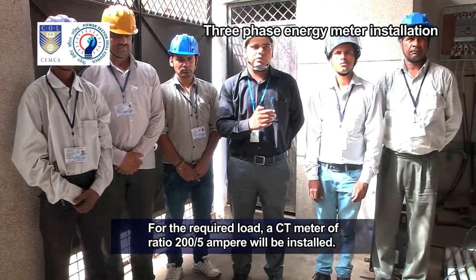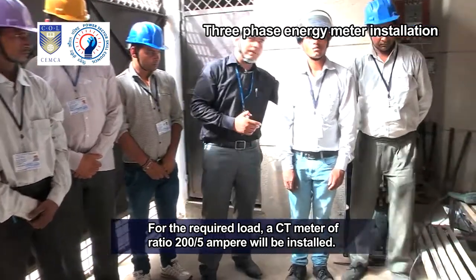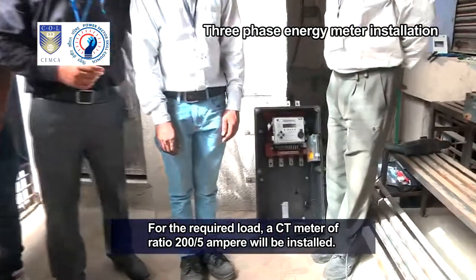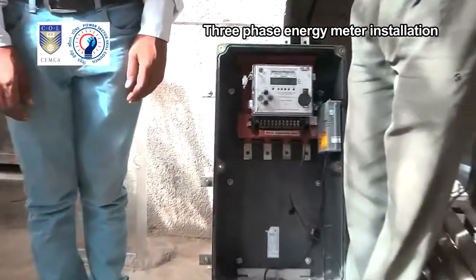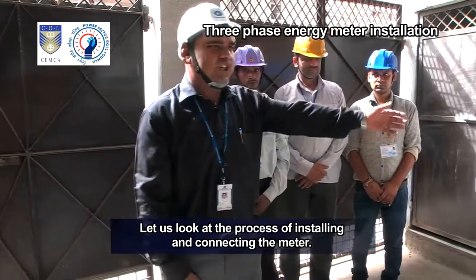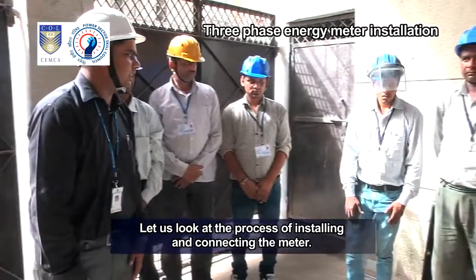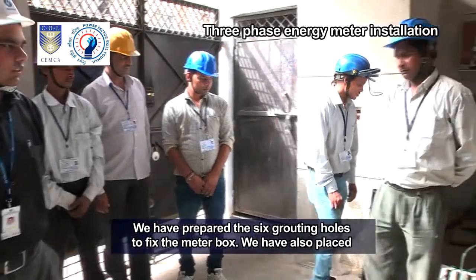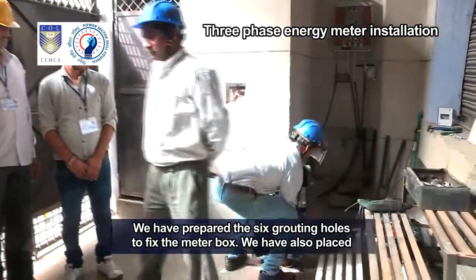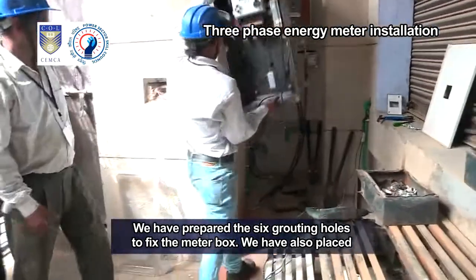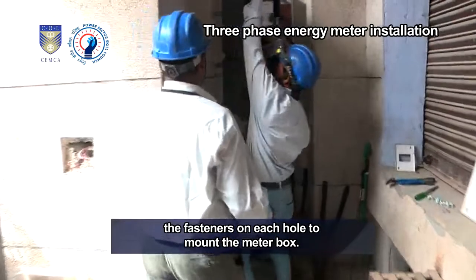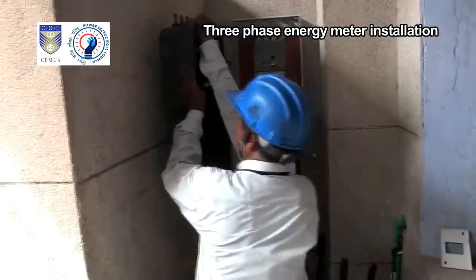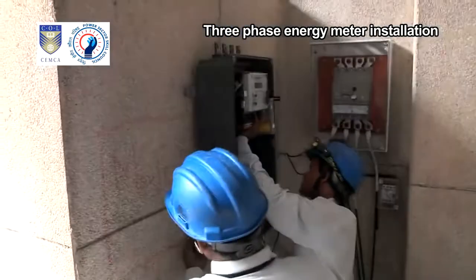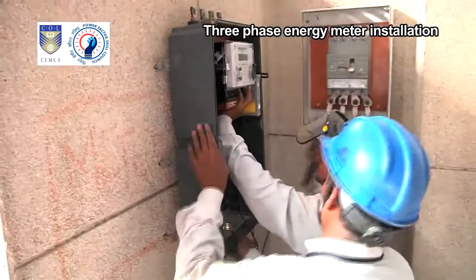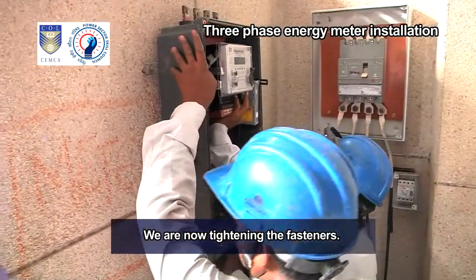For the required load, a CT meter of ratio 200 by 5 ampere will be installed. Let us look at the process of installing and connecting the meter. We have prepared the 6 grouting holes to fix the meter box. We have also placed the fasteners on each hole to mount the meter box. We are now tightening the fasteners.